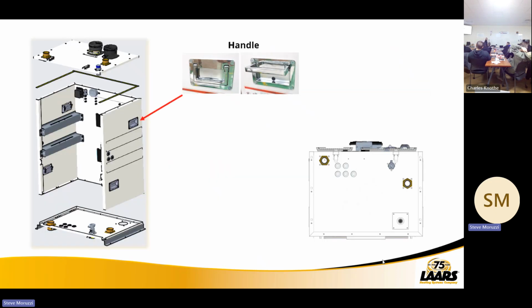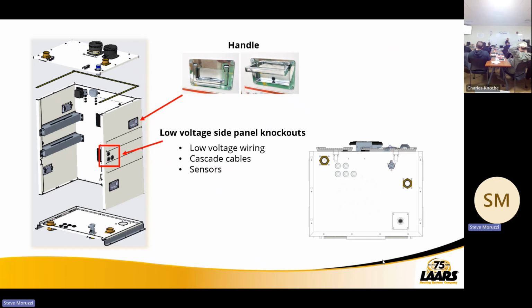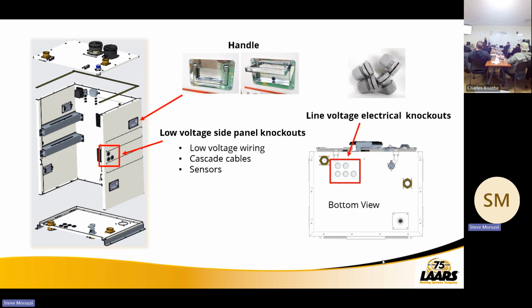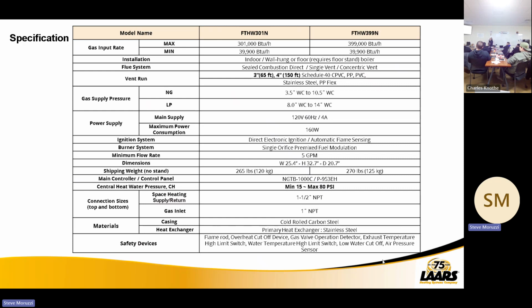So when you're cascading them and venting as well, we give you handles to lift these up and put them in position. You'll have knockouts for low voltage wiring, cascading cables or sensors on the side panels as well, and line voltage knockouts on the bottom. That's where your line voltage comes into the boiler or the appliance. Right. Condensate is also off the bottom.